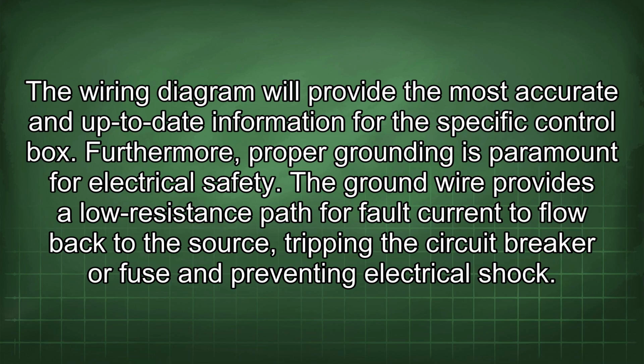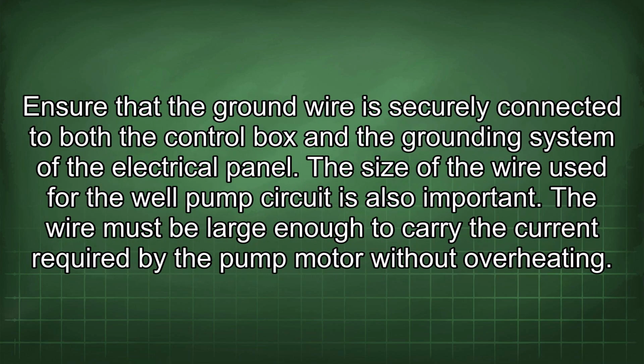Furthermore, proper grounding is paramount for electrical safety. The ground wire provides a low resistance path for fault current to flow back to the source, tripping the circuit breaker or fuse and preventing electrical shock. Ensure that the ground wire is securely connected to both the control box and the grounding system of the electrical panel. The size of the wire used for the well pump circuit is also important.